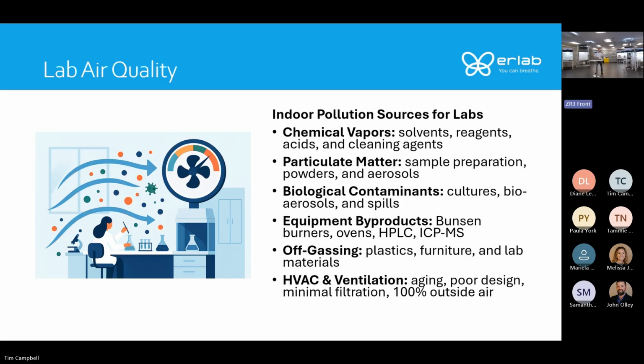So what happens when you have a poor air quality day outside? You bring all that into your lab space, especially during wildfire season. You bring all that smoke into your lab space because you have 100% outside air. You can't recirculate it and filter it through the rest of the building. That's all coming in. You have a nice weather front come through, get rid of all the wildfire smoke outside, but then you still have all that poor air quality inside.